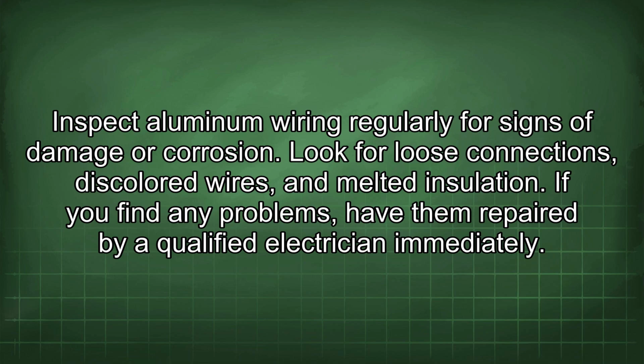Inspect aluminum wiring regularly for signs of damage or corrosion. Look for loose connections, discolored wires, and melted insulation. If you find any problems, have them repaired by a qualified electrician immediately.